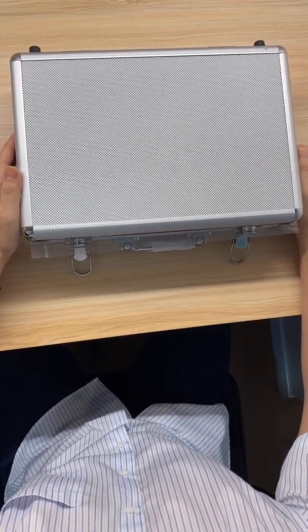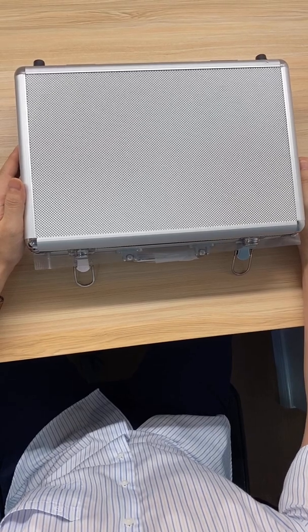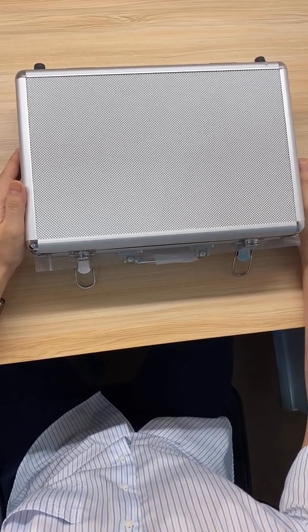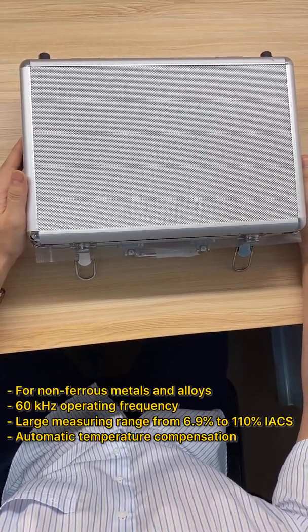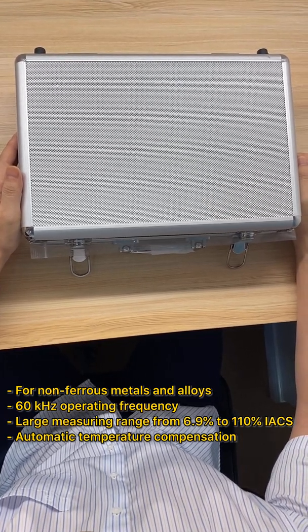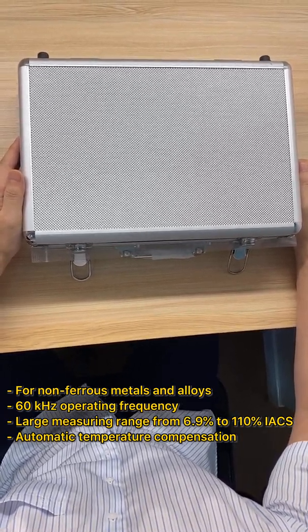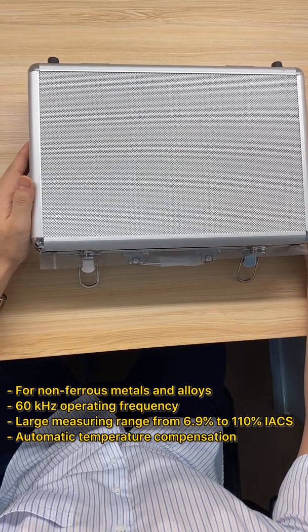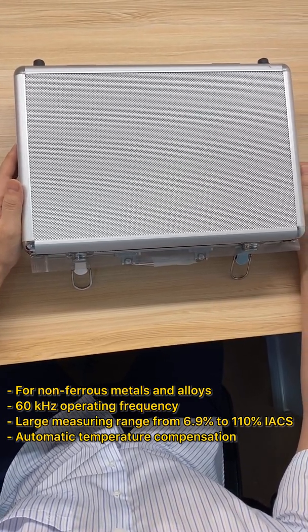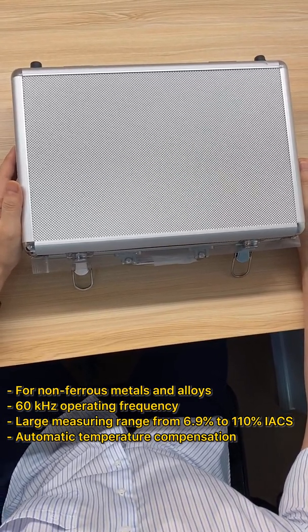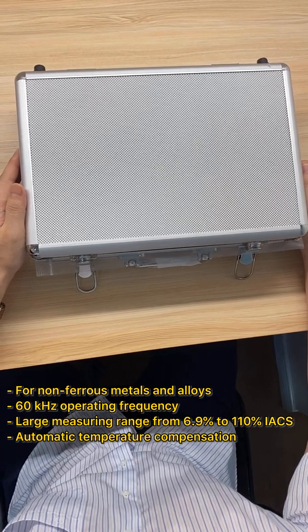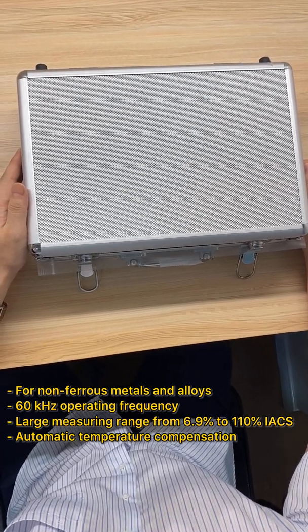This instrument is based on the eddy current principle, which can detect non-ferrous metals. It operates at 60 kHz working frequency and detects conductivity from 6.9% to 110% IACS, with automatic temperature compensation function.